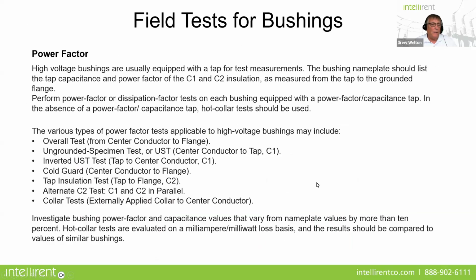Okay, so there are a couple of different tests that we want to run. For high voltage bushings that have the tap cover, we're going to do a C1 and C2 test, as measured from the tap to the grounded flange. You have to perform your power factor tests on each bushing equipped with the tap. And in the absence of the tap, we're going to use a hot collar test.